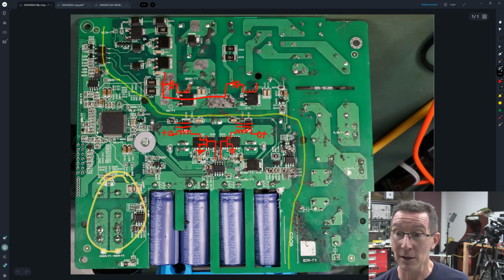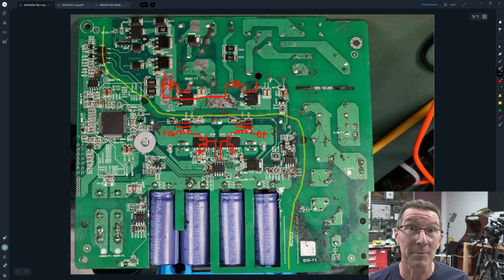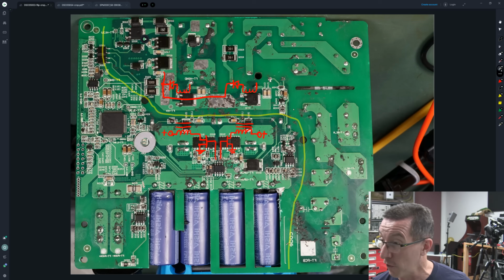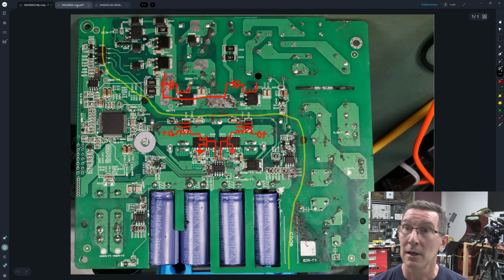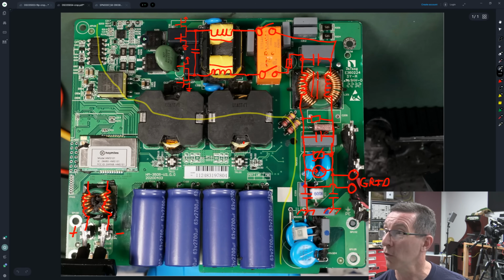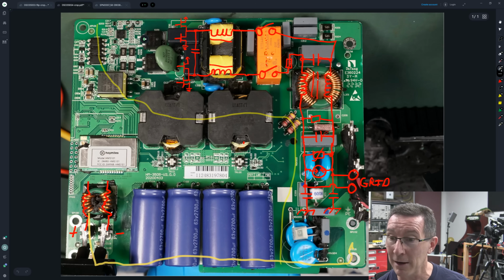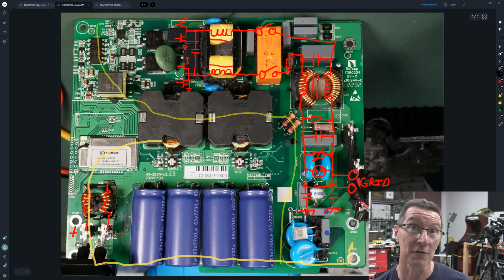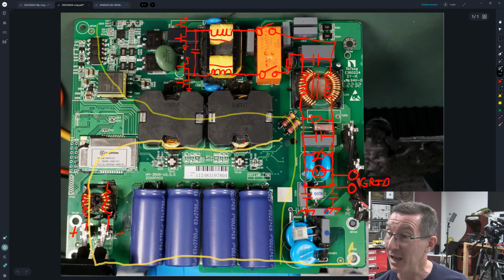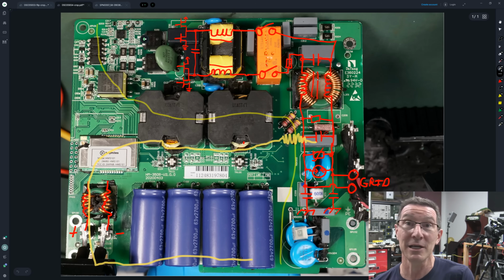You know, the solar panel, something's happened in this circuitry, something's happened in your physical install with your solar panels, which are all earthed, by the way. They're all earthed back to your mains earth and up here as well, so they're all connected. All your physical panels - if you get water ingress in your panels, you can get leakage from your mains earth through your solar panels back to this side. If you've got a failed solar panel, bad installation, water ingress, whatever it is, that's when you have to have galvanic isolation between there. That's when it actually matters.